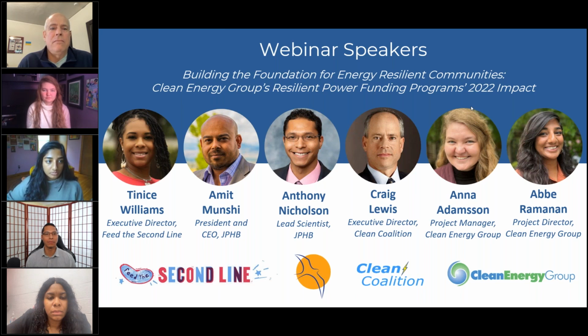Grid forming means it can send a sinusoidal wave signal just like the grid does, so all the loads think the grid is on. Basically the microgrid is acting like the broader grid. So it has to be able to do grid forming, and then black start is if everything goes down, the microgrid has to be able to bring the loads back up. The whole system needs to come back up, and that's what's referred to as black start.